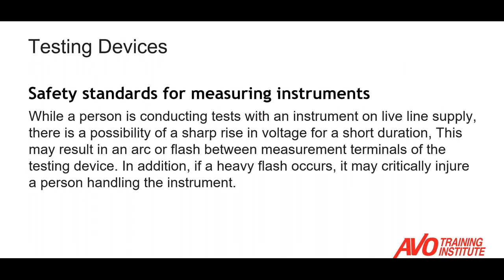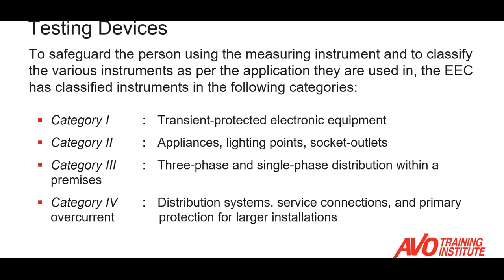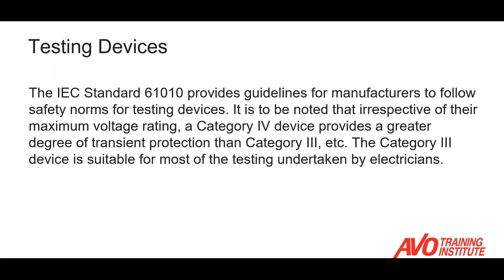What are some safety standards for test equipment? While a person is conducting a test on a live circuit, there's a possibility of a sharp rise in voltage for a short duration, which may result in an arc flash between the measurement terminals. If a heavy flash occurs, a person could be critically injured while handling the instrument. The IEC has divided multimeters into four categories depending on the environment, and a category four meter could be rated at a lower voltage than a category three meter. We need to review the manufacturer's documentation and make sure we have the right meter selected for the environment.